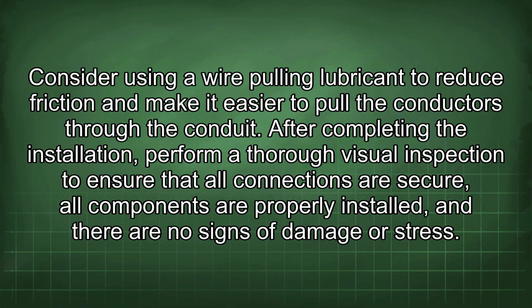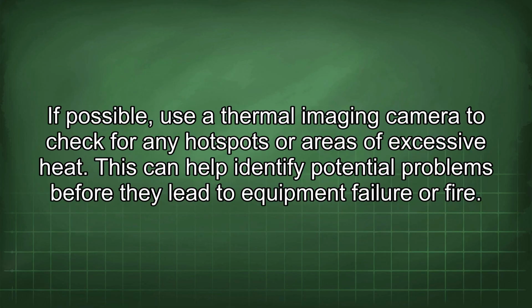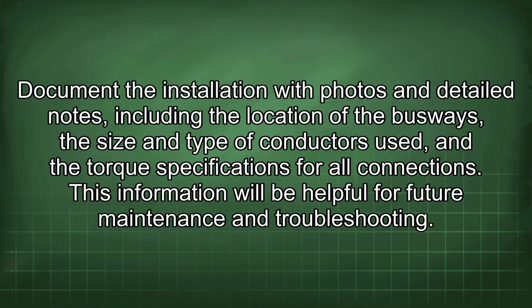After completing the installation, perform a thorough visual inspection to ensure that all connections are secure, all components are properly installed, and there are no signs of damage or stress. If possible, use a thermal imaging camera to check for any hotspots or areas of excessive heat. This can help identify potential problems before they lead to equipment failure or fire. Document the installation with photos and detailed notes, including the location of the busways, the size and type of conductors used, and the torque specifications for all connections.